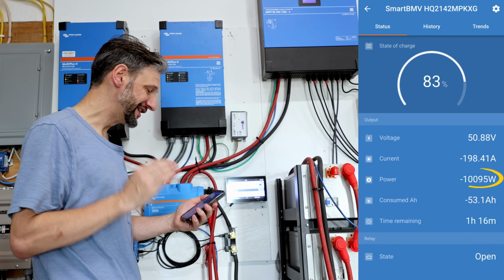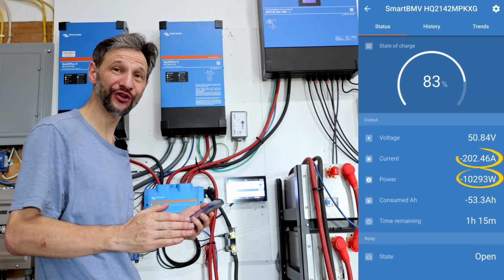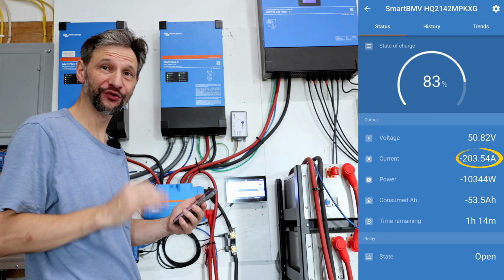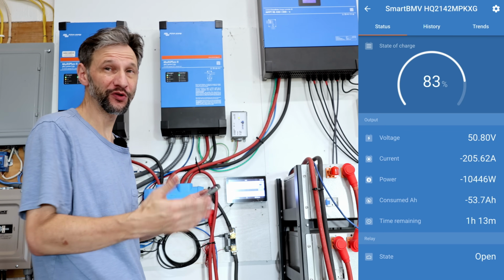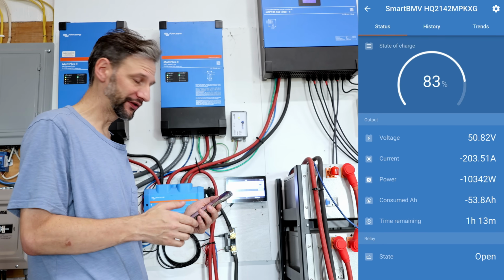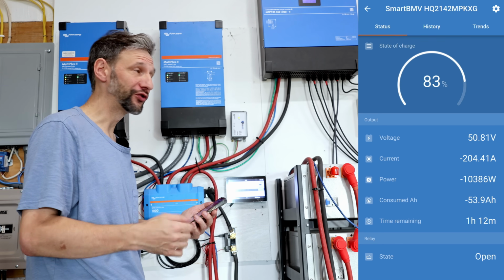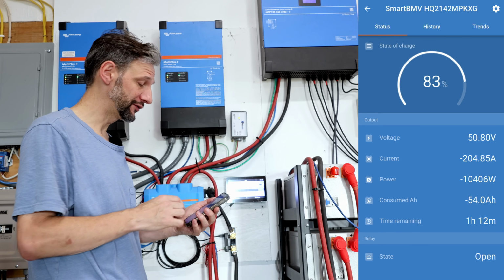Ooh, there we are. 10,000 watts, 200 amps. Let's check the Basen Green BMS and see. It's probably showing a little more than that because we're measuring outside of the battery. We're going to run that for a little bit and check it with the infrared camera and see what it looks like.